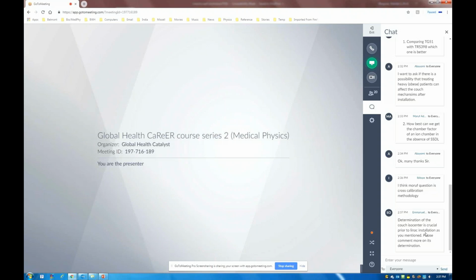Great. Prior to Linac installation, as you mentioned, please comment more on its determination. So we usually don't determine it. This is done by the manufacturer. Varian comes in and puts that in. Once the Linac is installed, that's the only time you can determine that, because you need some sort of light field or radiation field to determine the ISO center of the couch.